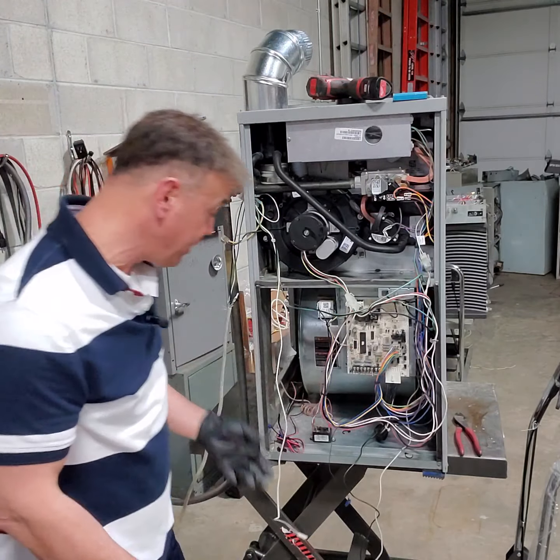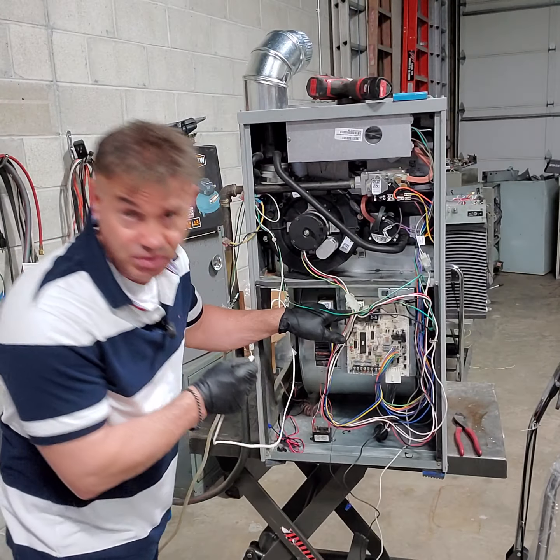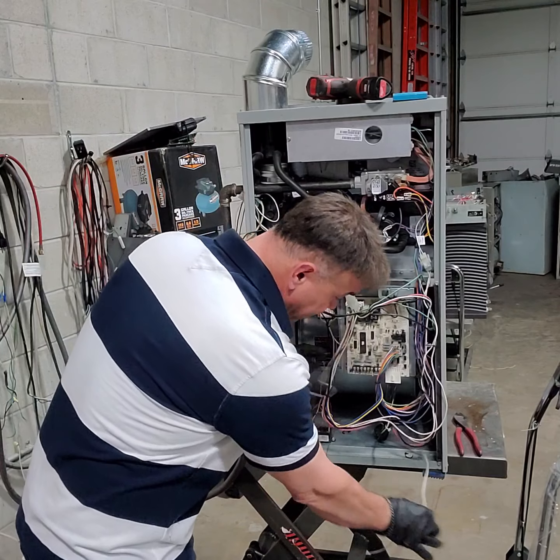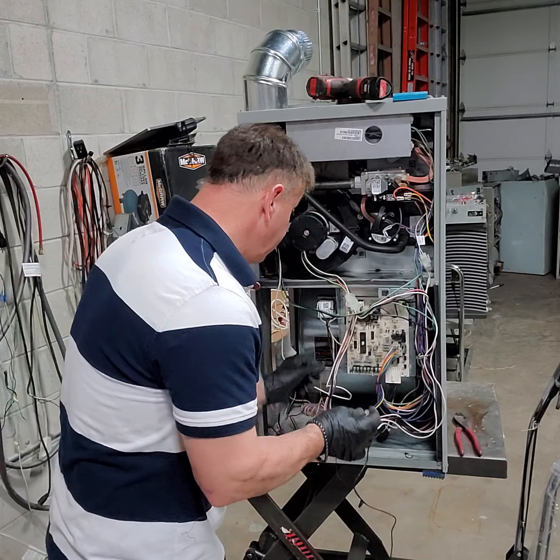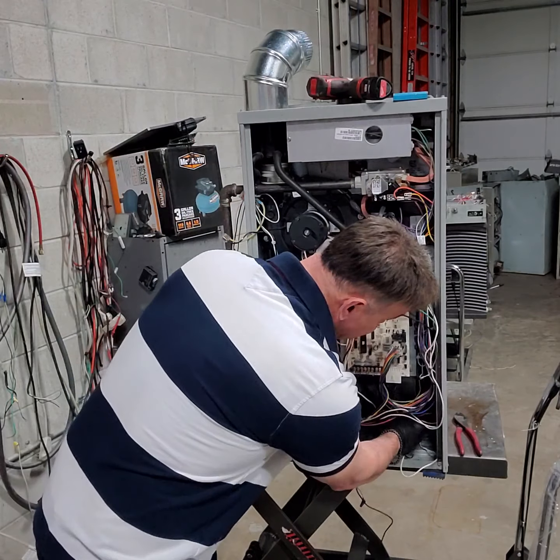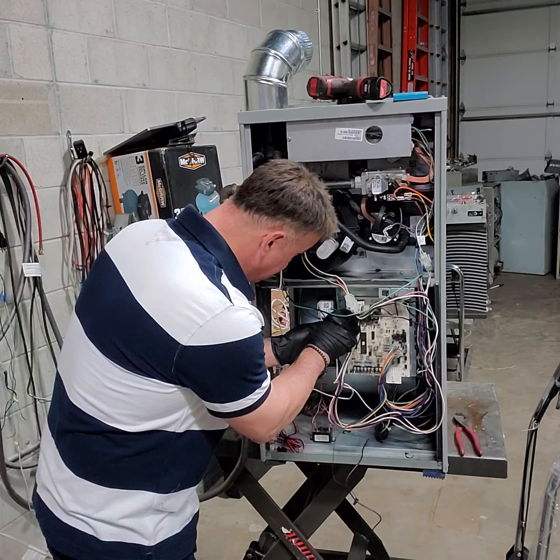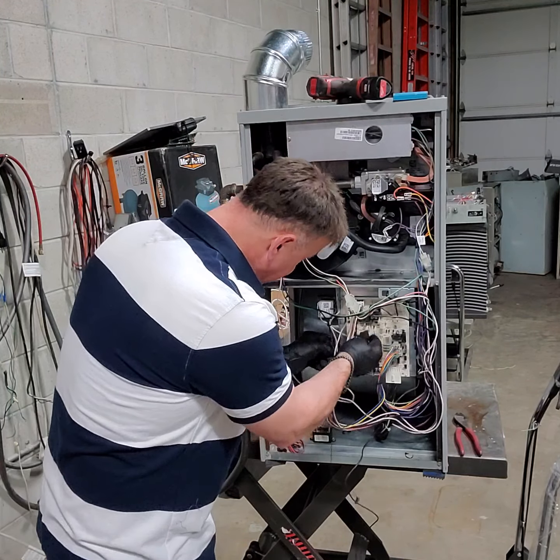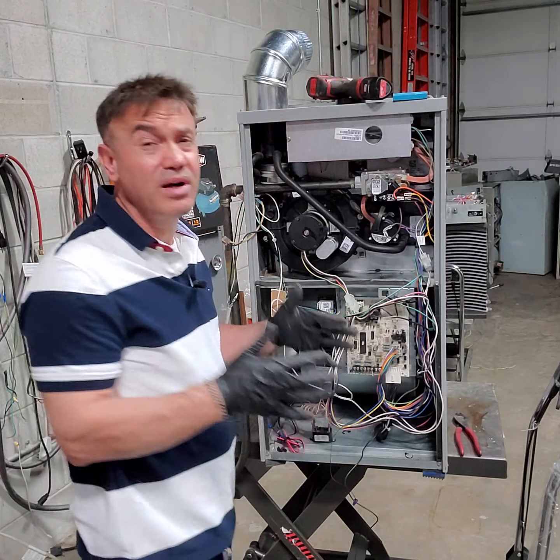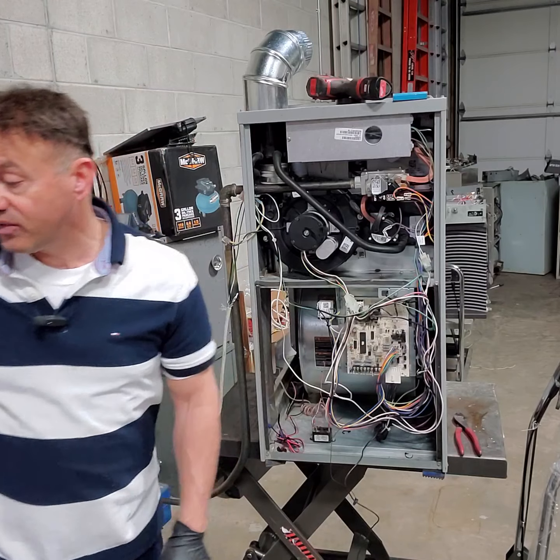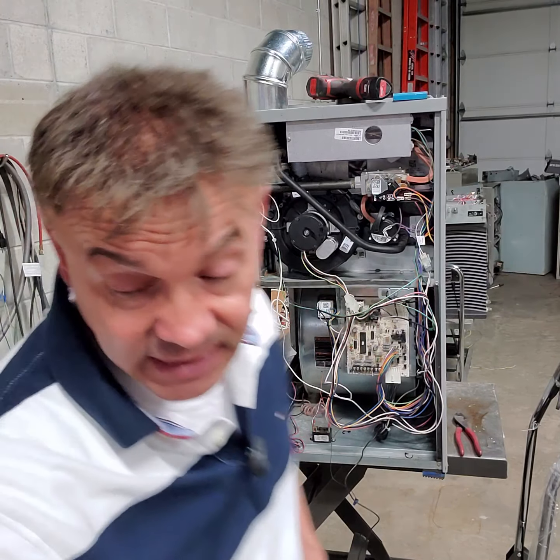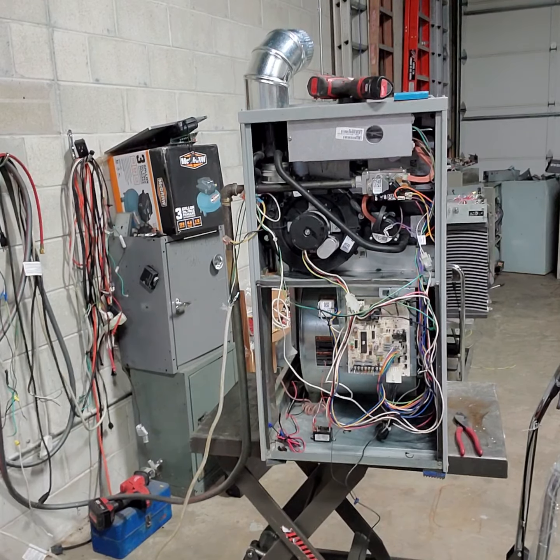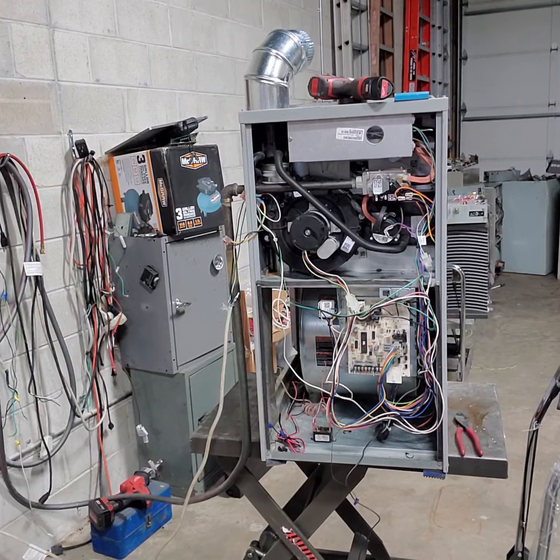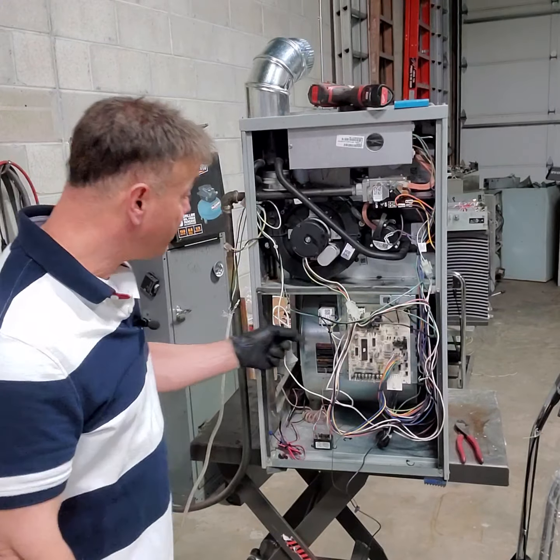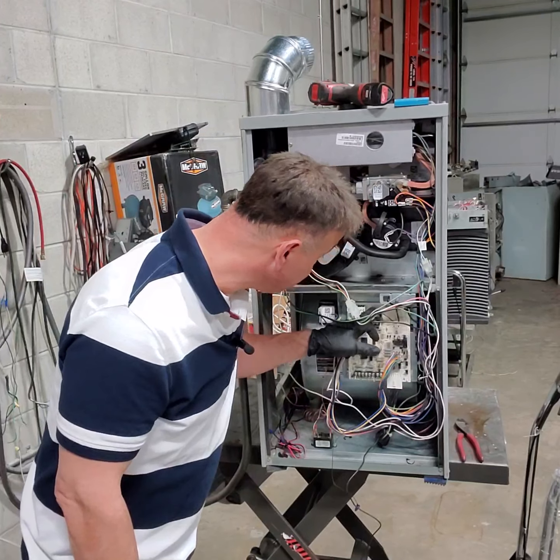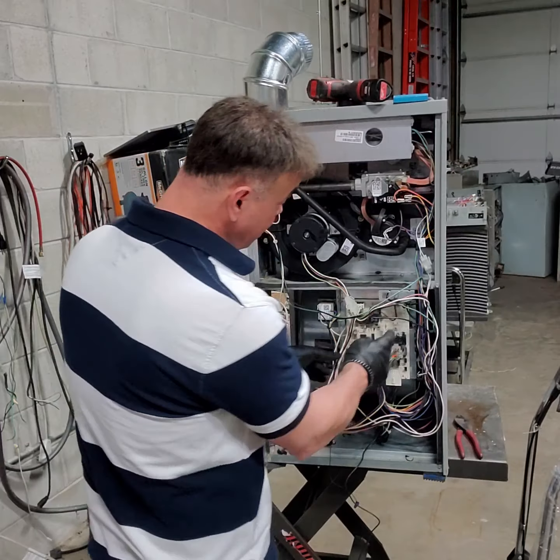Now we're going to go to common - all the whites, because they go into the neutral area. So we've got the power line, this is the blower, and then the transformer, usually these are the main 24 volts. Now, if you have a humidifier, it usually uses a transformer connection to the humidifier - I don't have one here, I had one earlier. If you want to use a humidifier, use a neutral from here, and it has a humidifier connection next to the power line. That finishes the whites.